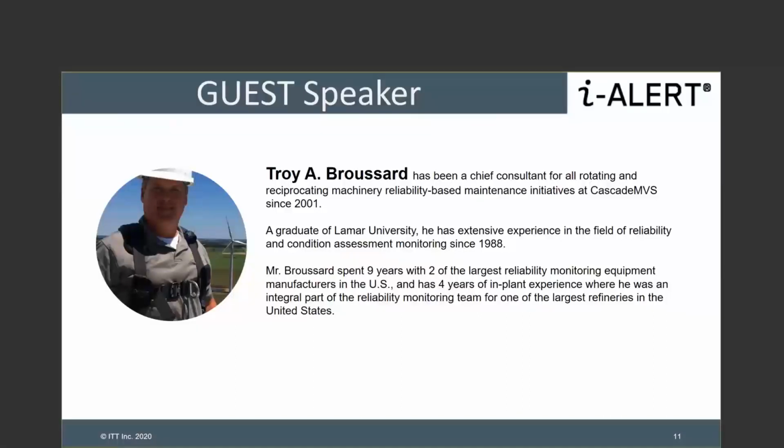Within less than 2 months, the vibration started trending up. It was their only machine, so the client, with a smart device using their Android phone, was able to go look at the data themselves. They didn't understand what we would call the squiggly lines, but they understood the trends. They said, hey, this is trending up, let me send you the data. They screenshotted some of the data the first time, and we said, well, let us come out and check it.